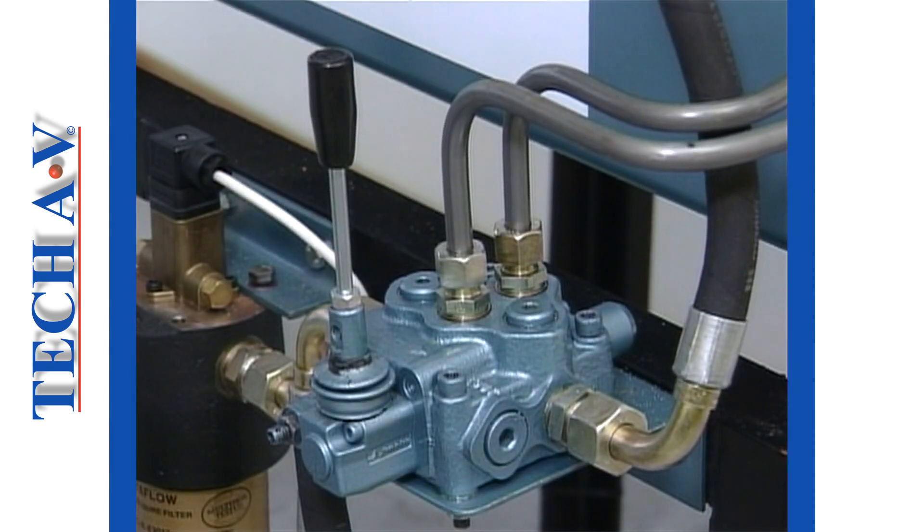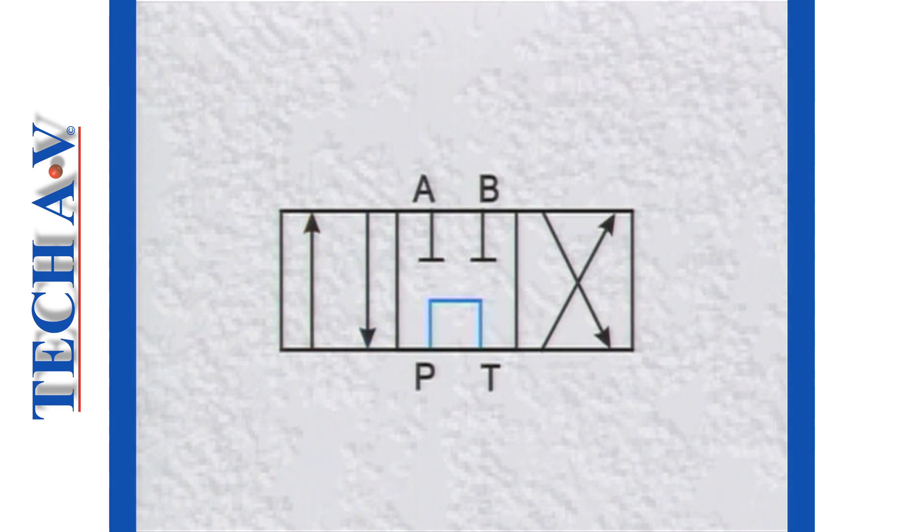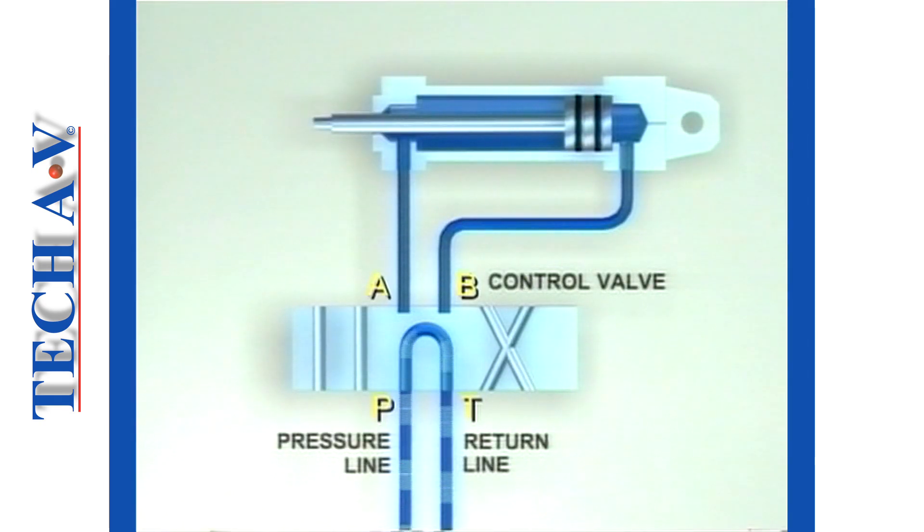In the center, or neutral position, oil flow from the pump is routed directly back to the tank. Both the A and the B ports are blocked. In this position, the pump's delivery is diverted back to the tank, or, if required, could be tandemed to another control valve.